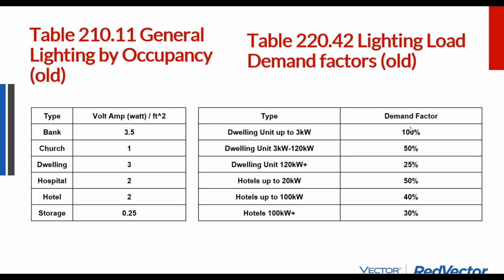Okay, so we talked about our load tables. These are what they look like. They vary by function, they vary by size, and there are discount factors for the larger the building gets. And so, if everyone in the hotel turns on their air conditioner at the exact same time, you might end up tripping the main breaker for the entire building, because they've assumed that that isn't going to happen. Say for hotels, once the load calculations start to get above 100 kilowatts, you can start discounting that load by 70%.